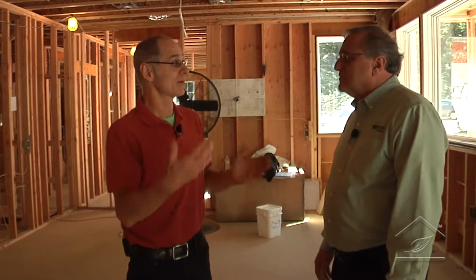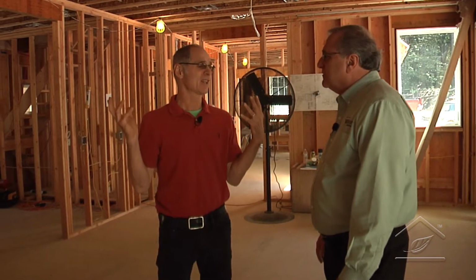Okay. Yeah, I guess in the South they do a little more of the energy recovery, but up here I picked an HRV. And what that is, we're going to pull from the kitchen and the bathrooms. We think those are the odor-producing areas and exhaust that out, but take the heat out of it and then replace that air back in the common, like the return ductwork of the HVAC system. So your unit that does that exchange of heat with the air moving out and the air moving in, where's that located? Actually, we have it up in the attic.